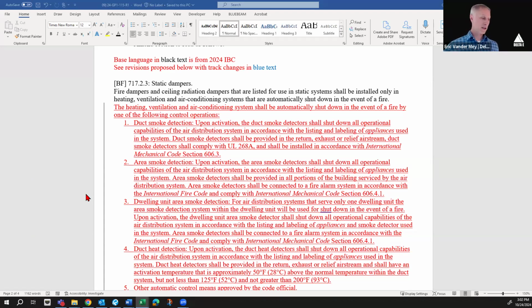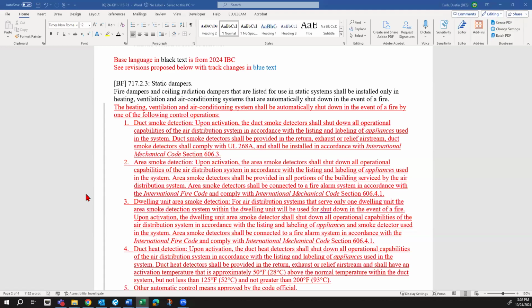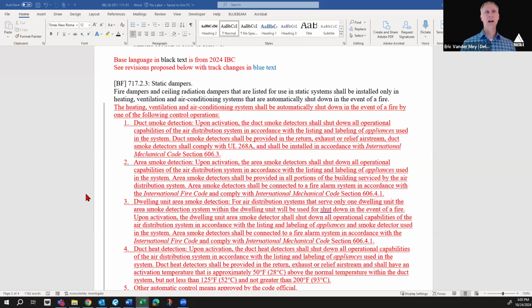Are you talking about the ceiling radiation dampers or the shutdown devices? The shutdown devices - well, like I said, things like duct smoke detectors are UL listed for certain duct sizes. So maybe if you have a 12-inch round duct, that would be acceptable, but if you have a 6-inch duct, there aren't detectors for really small ducts - that needs a certain duct velocity and size. As far as area smoke detectors, my understanding is there's not an area smoke detector that is UL listed to directly control the shutdown of an HVAC system. So that signal from the area smoke detector has to go back to your central fire alarm system, and then that fire alarm system has to shut down that HVAC device.